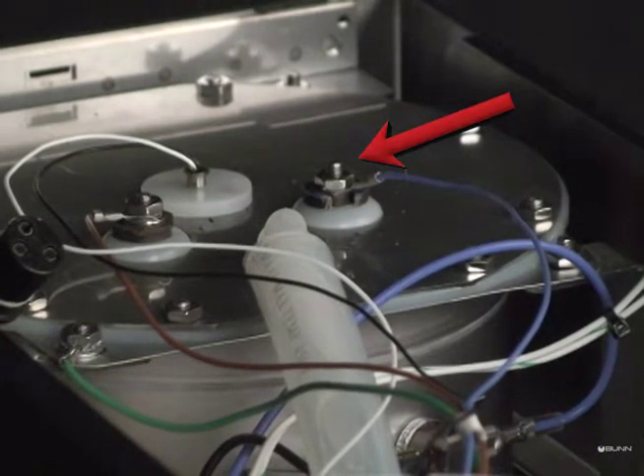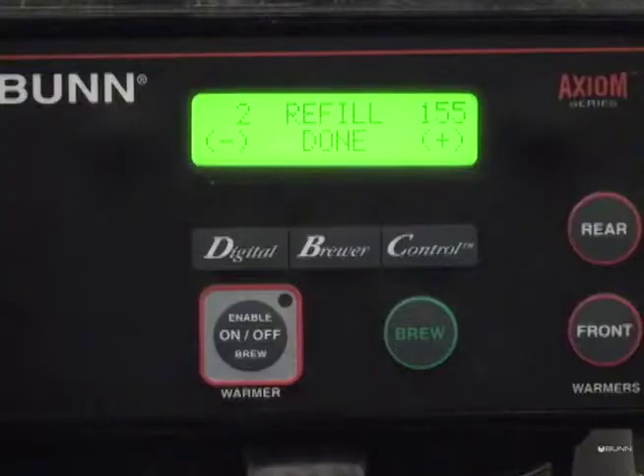The long liquid level probe with the blue wire is the main refill probe circuit which has a direct correlation to the refill threshold menu. This number shows the actual condition or conductivity of the water when in contact with the long refill probe. A low left number typically ranging from 0 to 4 means there is no need for an adjustment. A high left number typically ranging from 50 to 140 means you may need to adjust refill threshold.